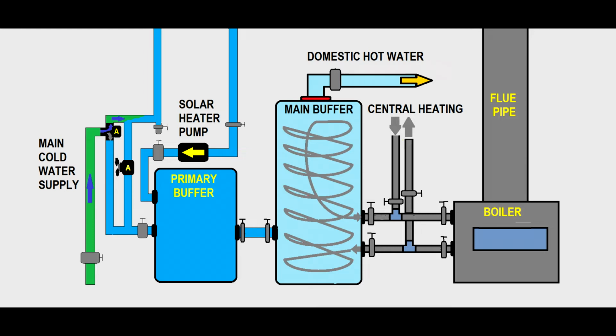In winter, it will direct the water flow directly into the primary buffer, because we have to make the solar heater system redundant—we have to drain it, otherwise the water might freeze, and as the ice expands it can destroy the tubes. But in summer, that three-way valve will direct 90% or more of the water onto the solar heater panel, and only about 5 to 10% into the primary buffer.